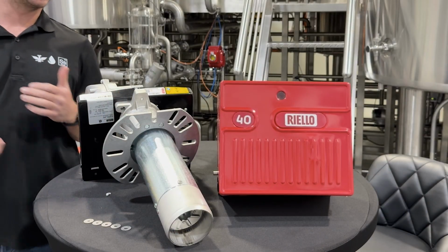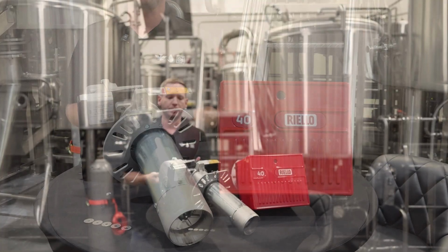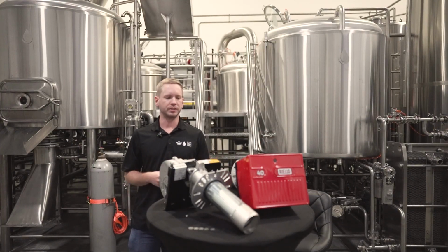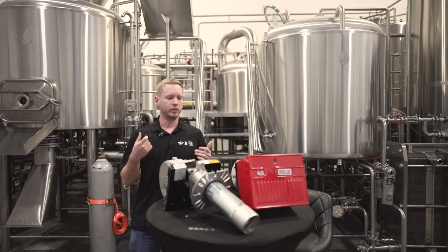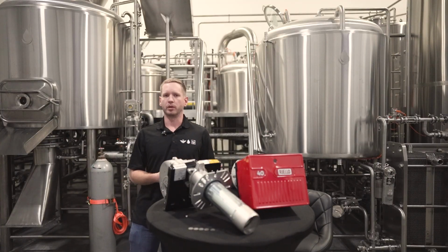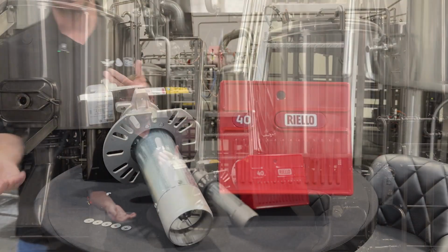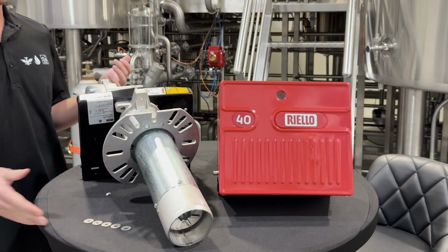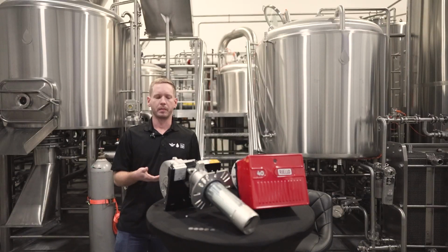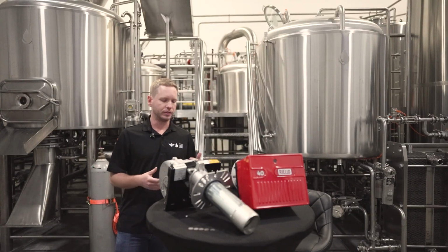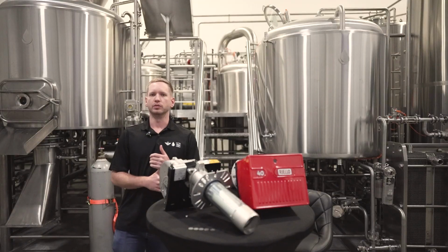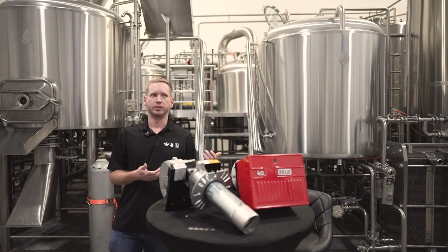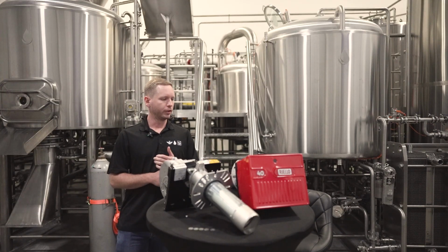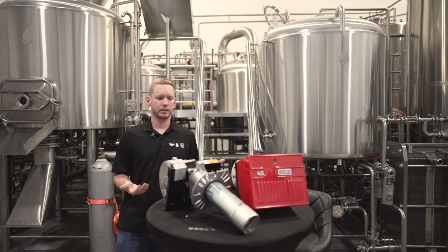A couple other things to consider. Each burner does come with some orifices. Your Deutsche technician or project manager who installed your brew house should have placed the right orifice. However, if for whatever reason you're still seeing some issues with gas mixture, or your burner just continues to trip, it would be worth it to get a burner tech out there or call Deutsche ourselves and ask about these orifices. These orifices just provide the correct mixture of gas going into your burner. A few other things, some electrical components can go out. We do use relays on these, a 24 volt or 120 volt relay. That's something you can always call Deutsche about and we can really help you out. But for the most part, that's a quick breakdown of Riello burners.